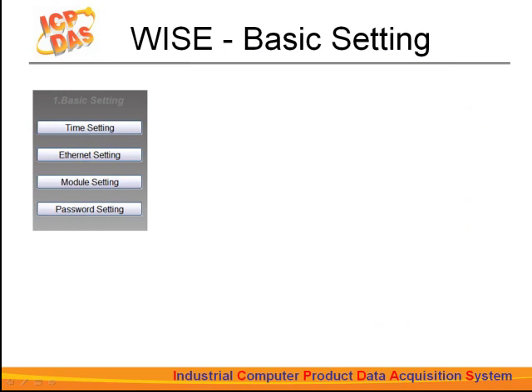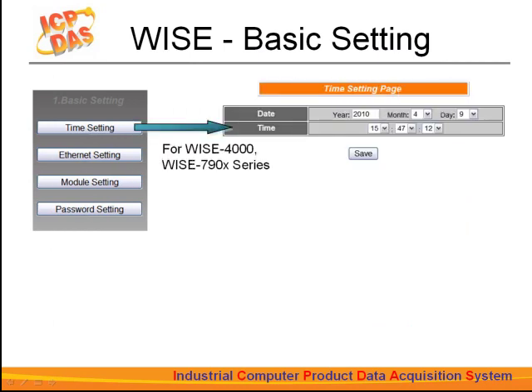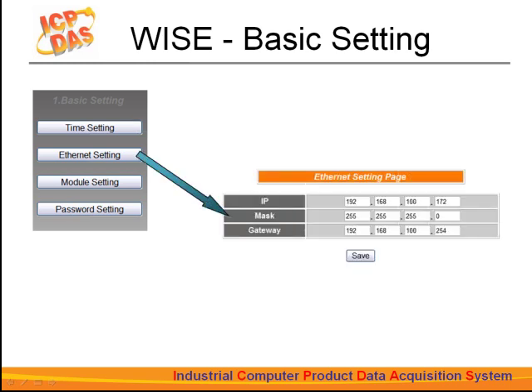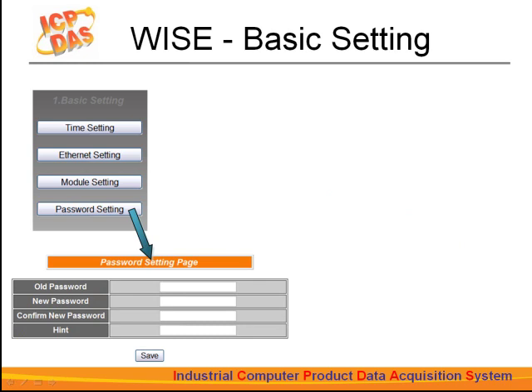For basic settings, first let's talk about the time setting, so you can adjust the time for the controller. This function only applies to modules with real-time clock functions. Ethernet setting is for IP mask and gateway settings. If you don't want your settings to be modified by unauthorized users, you can set up a password to prevent unauthorized access. After the password has been set, anyone who tries to upload logic rules to the controller will be asked to input the correct password. The default password is set to 'wise' in lowercase.